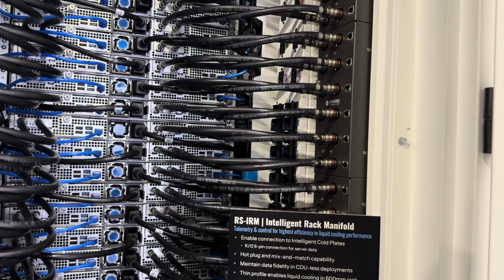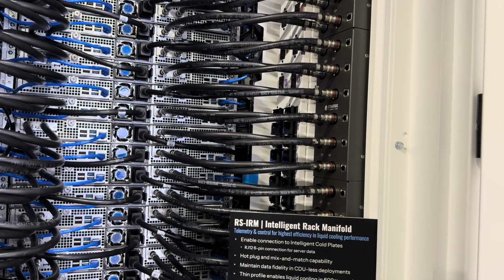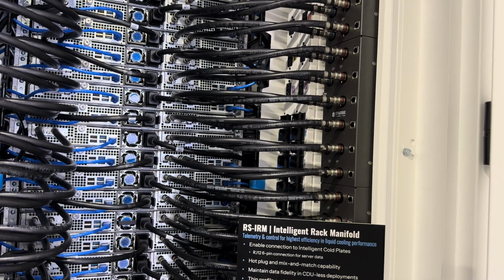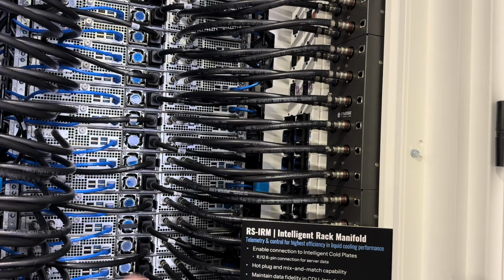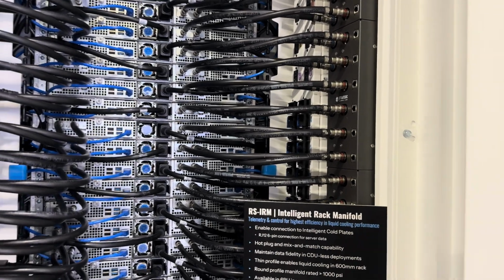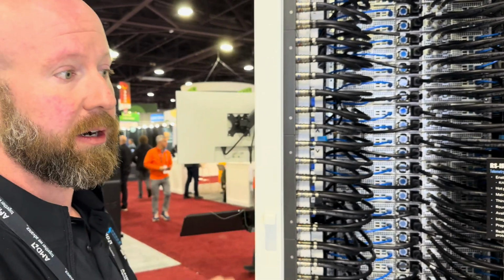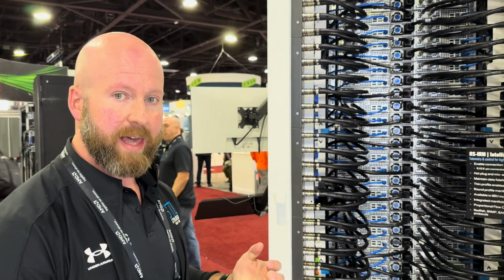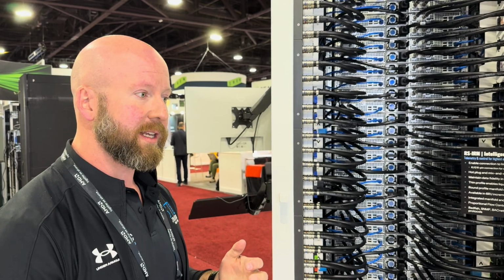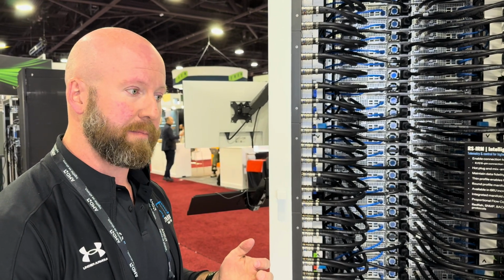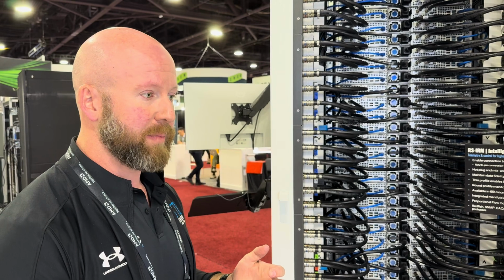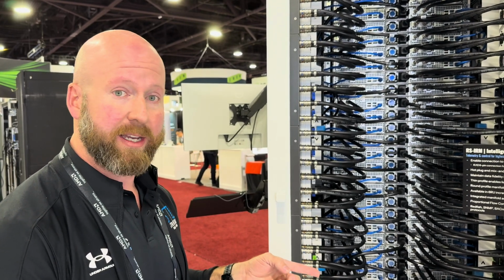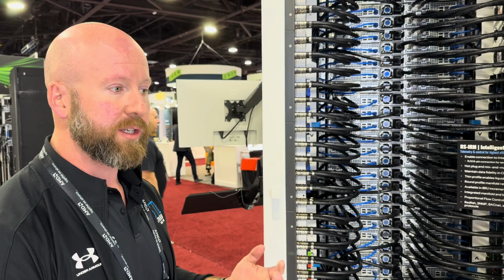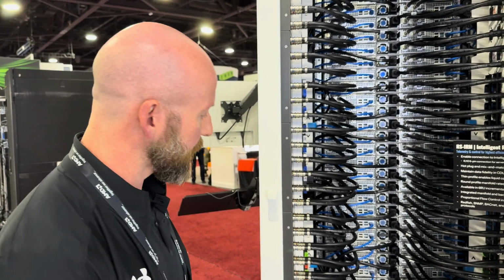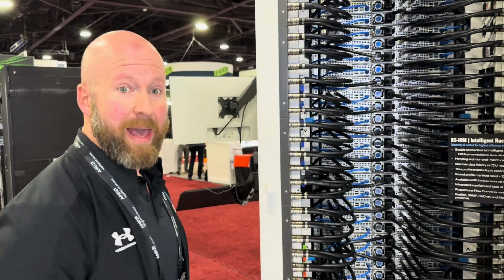Additionally, we have other versions of this same manifold where we can put flow control valves at each individual server location, and if we happen to have a leak incident, as an example, we can turn off water and isolate it to that server without impacting the rest of the rack. This gives us the ability to do closed loop feedback on component temperatures. It's important that, as liquid cooling grows and scales, we stop overcooling devices and actually start cooling them based upon real-time consumption. Without the ability to extract processor temperature data and use that to control pump speeds and valve settings, we're always going to be in an open loop environment that wastes power. So that's our back of rack manifold.